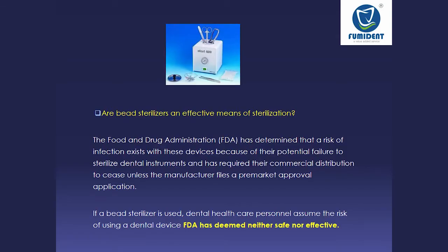So in the section of sterilization, I want to cover one more topic, that is the glass bead sterilizer or glass bead autoclave. The question is, are glass bead sterilizers an effective means for sterilization? In short, the answer is, according to the FDA, these sterilizers are neither safe nor effective for sterilization procedures.